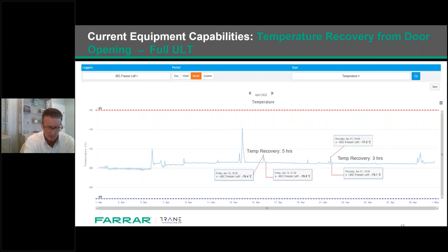But also pay attention to the temperature spikes, as, again, they paint the bigger picture about your process in the door opening. So as most of you may have a central monitoring system, I often recommend, in looking at the freezer, what we call the freezer heartbeat, right? So this is where you should see the on-off control that are clearly visible on the left side of the graph here. And however, your data logger, if it shows a flat line, this is, in this case, a clear indication of a possible system failure in the near future, or possibly ice buildup on the door gasket, right? So this is where we mentioned a few slides ago that having ice buildup on the door gasket infiltrates warm air, and then the warm air causes the system to keep operating.